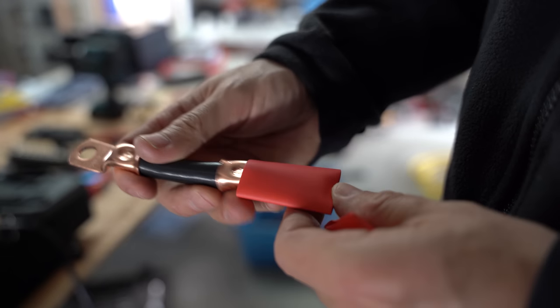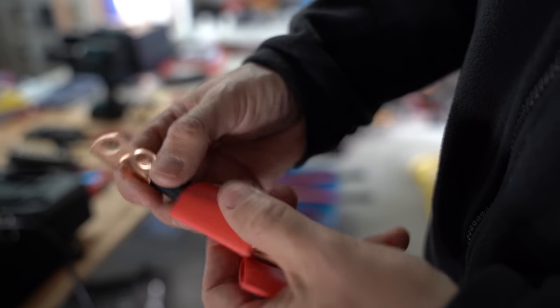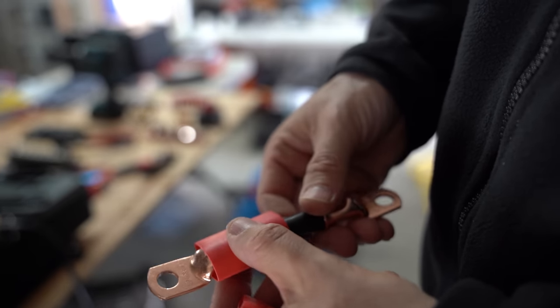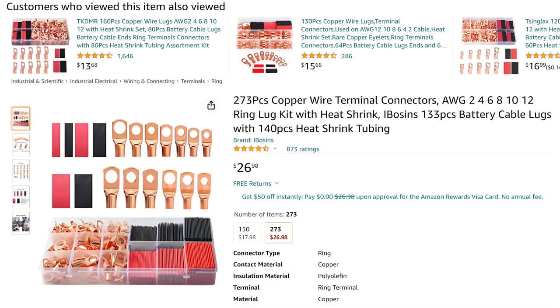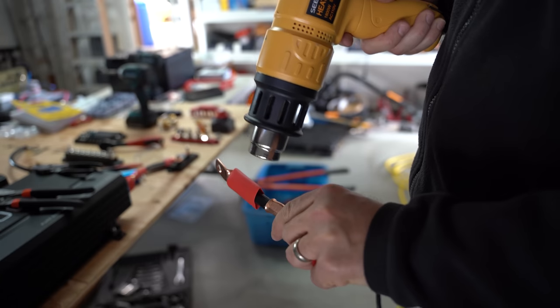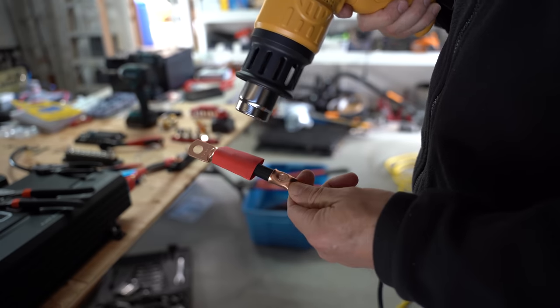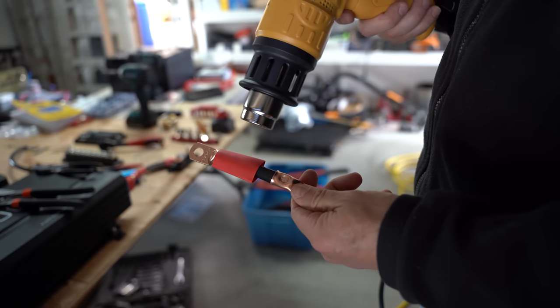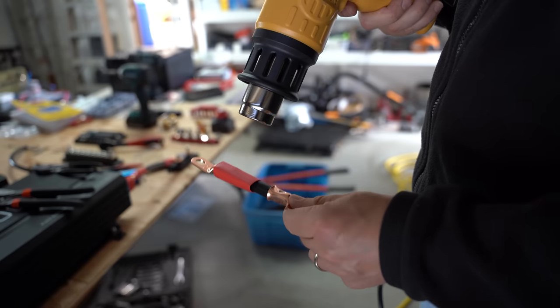Next, we need to add shrink wrap to the wire so that we're insulating and protecting the area where cable lugs and wiring connect. These kits you order online will typically come with these. You can use either a cigarette lighter to apply heat to these, or as shown here, use a heat gun. But be careful as these will get very hot.